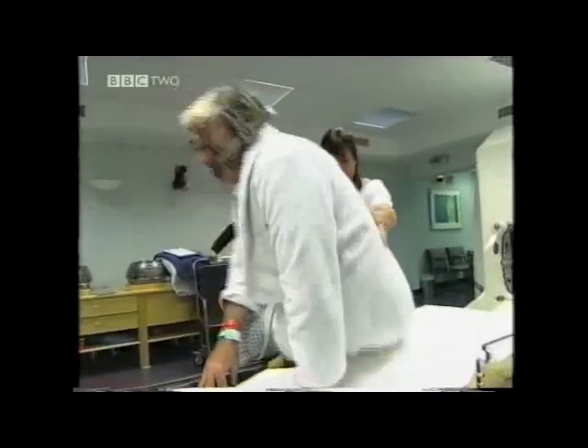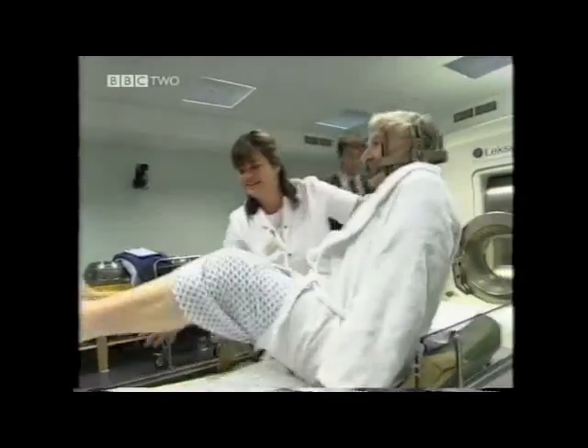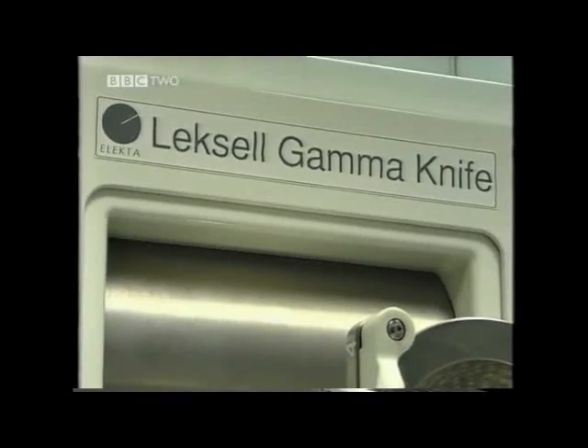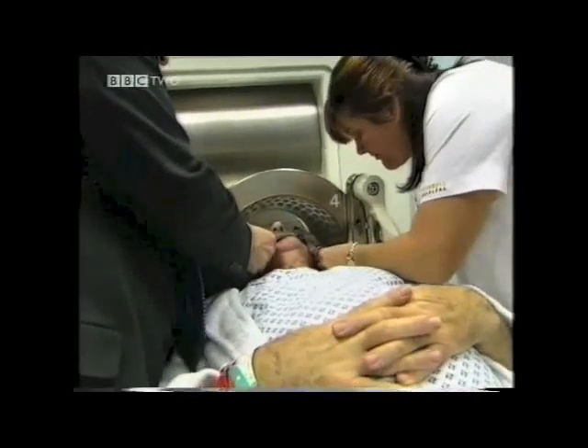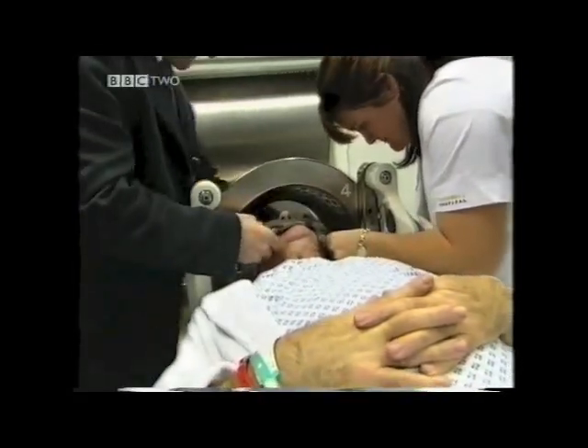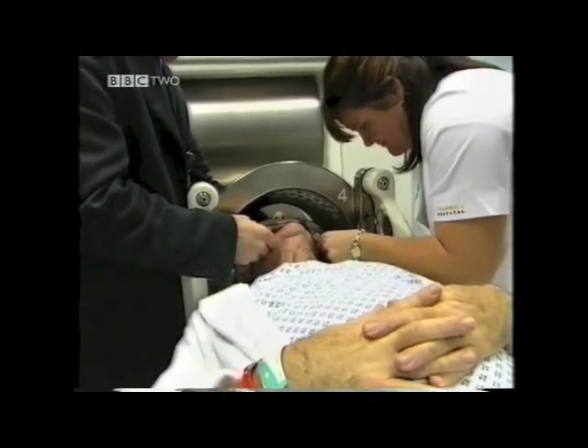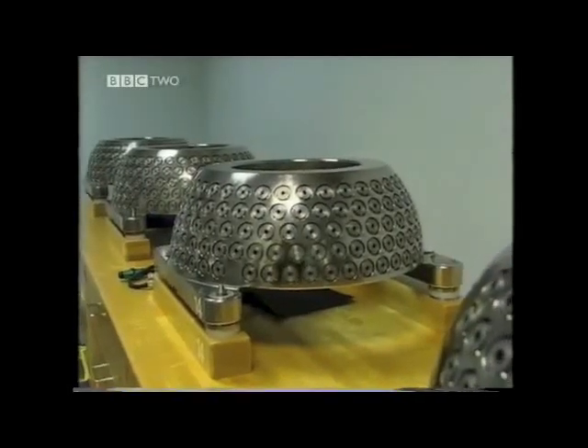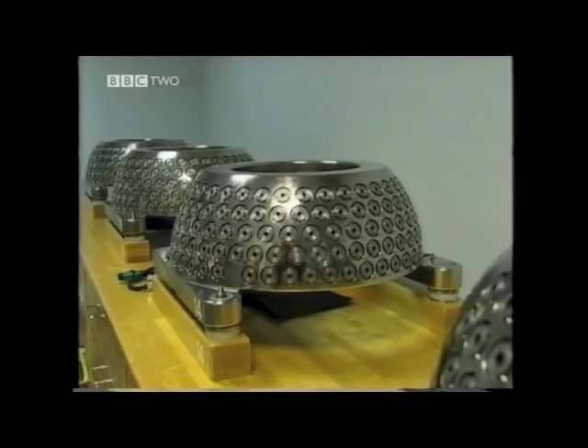The next stage in treatment is the patient going into the gamma knife itself. The patient lies on the treatment couch and their frame is attached firmly inside the collimator helmet. Now, the collimator helmet focuses 200 beams of gamma radiation in a very fine focus, which has an accuracy of better than half a millimetre. The collimators are made out of tungsten, which is a very dense material which absorbs radiation.